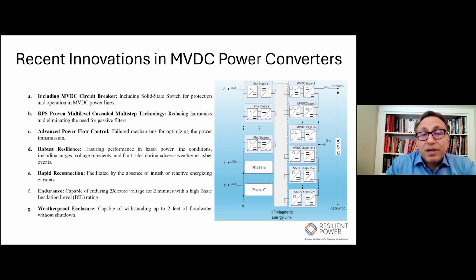That has been reduced in our design, because when you increase the frequency, all the magnetics are decreased in basically the same ratio. If you increase the frequency by 10 times, all the magnetics and filtering requirements are decreased by 10 times as well. The way this system works, we convert the medium voltage to multiple DC voltages, and then those multiple DC voltages are converted to high frequency, and the high frequency energy is pulled into the high frequency magnetic energy link. All of these power modules are linked through that energy link. If one of those power modules needs some energy, it takes from that pool. If it has extra, it puts it back into the energy link.